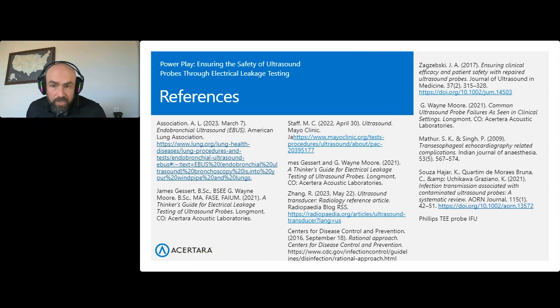Nicholas asked about the conductivity testing. So actually, conductivity and electrical leakage testing are used often interchangeably. So we're talking about the same thing in looking at that. Sometimes manufacturers will recommend an air leakage test. That's different than what we're discussing.